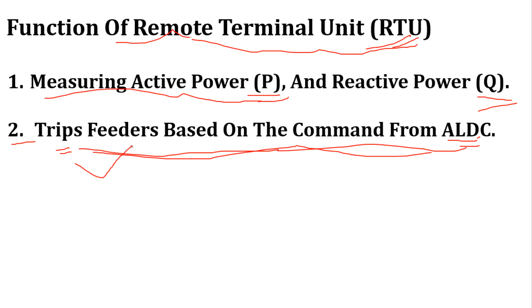Now, last one is the function of RTU, remote terminal unit. Its function is to measure the active power and reactive power continuously, and the next function is to trip the feeder based on the command from ALDC. That means if there is any fault in a particular feeder, then to isolate that feeder, RTU has to take a command from ALDC. If ALDC gives the confirmation about the tripping, then only RTU will trip the feeder. So RTU needs a command from ALDC to trip any feeder. That is the function of RTU.